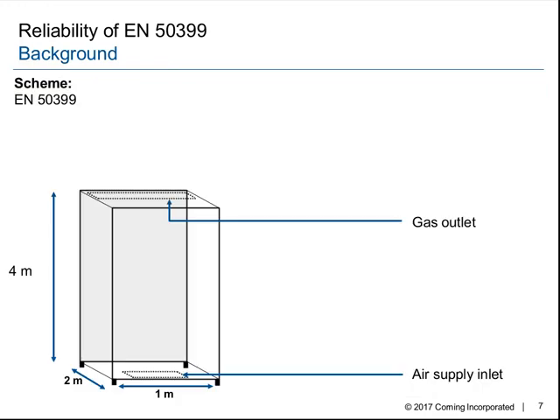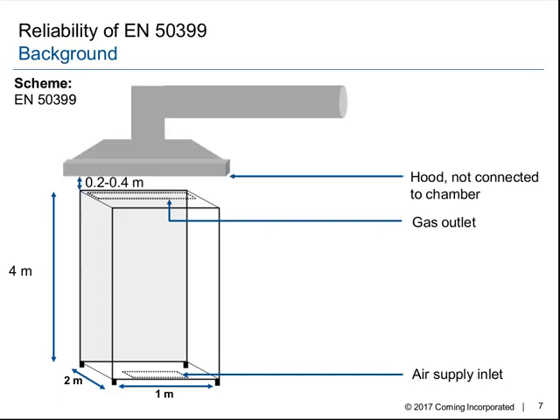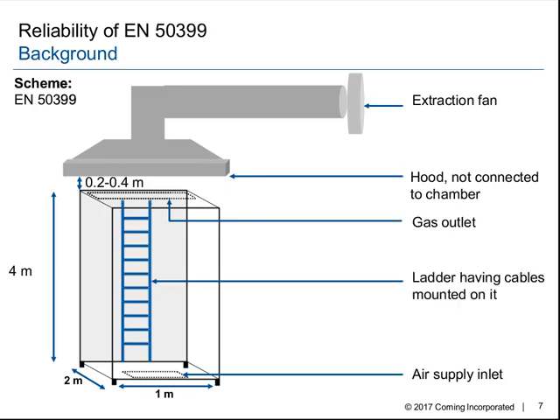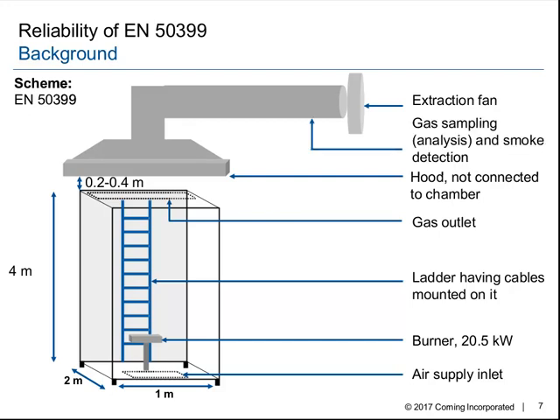The test in the end is an oven 4 meters in height with the air supply inlet on the bottom and the gas outlet in the top of the chamber. Above the chamber is a hood not connected to the chamber. In the end of the exhaust pipe is an extraction fan. In the back of the chamber is a ladder with the cables mounted on it. In front is a burner with a 20.5 kilowatt flame. And in the end of the exhaust pipe is a gas sampling where the heat and the smoke release parameters are determined. So the first thing we were asking ourselves is, what is the repeatability of this test?